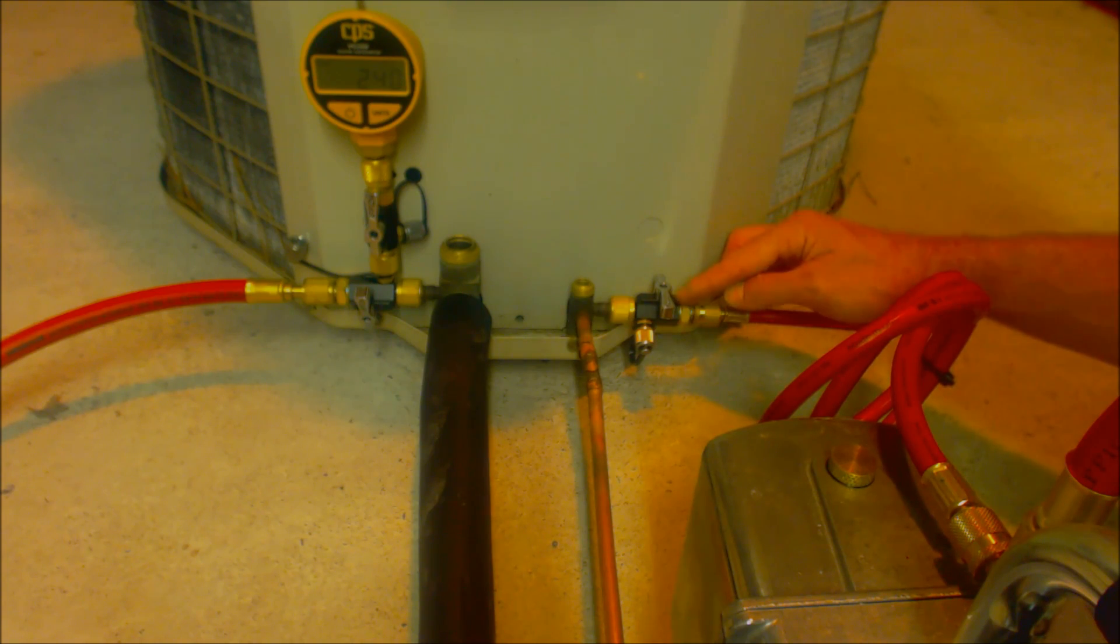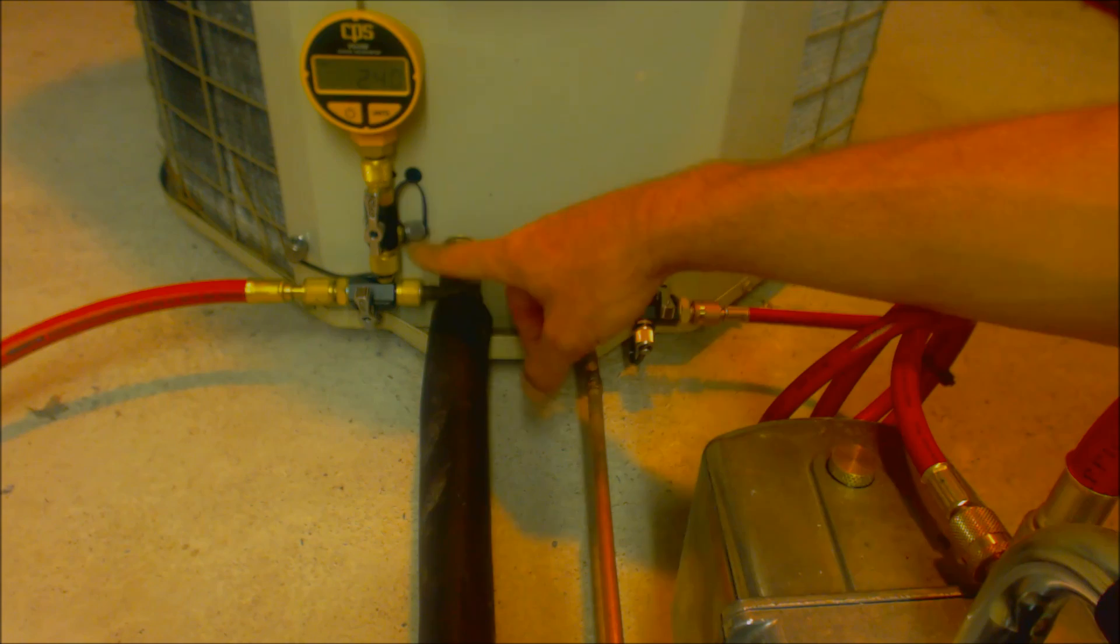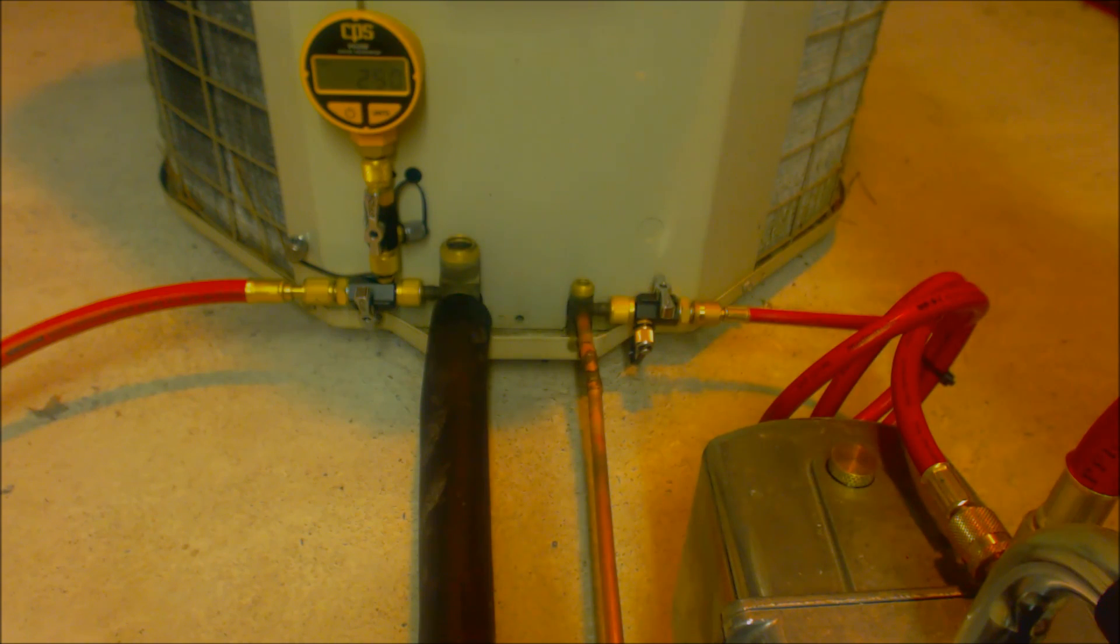These valve core removal tools here are rated down to 20 microns. It's real important that the valve that you're using is vacuum rated. That's why we're using a third valve core removal tool and not a hose with a valve on it.